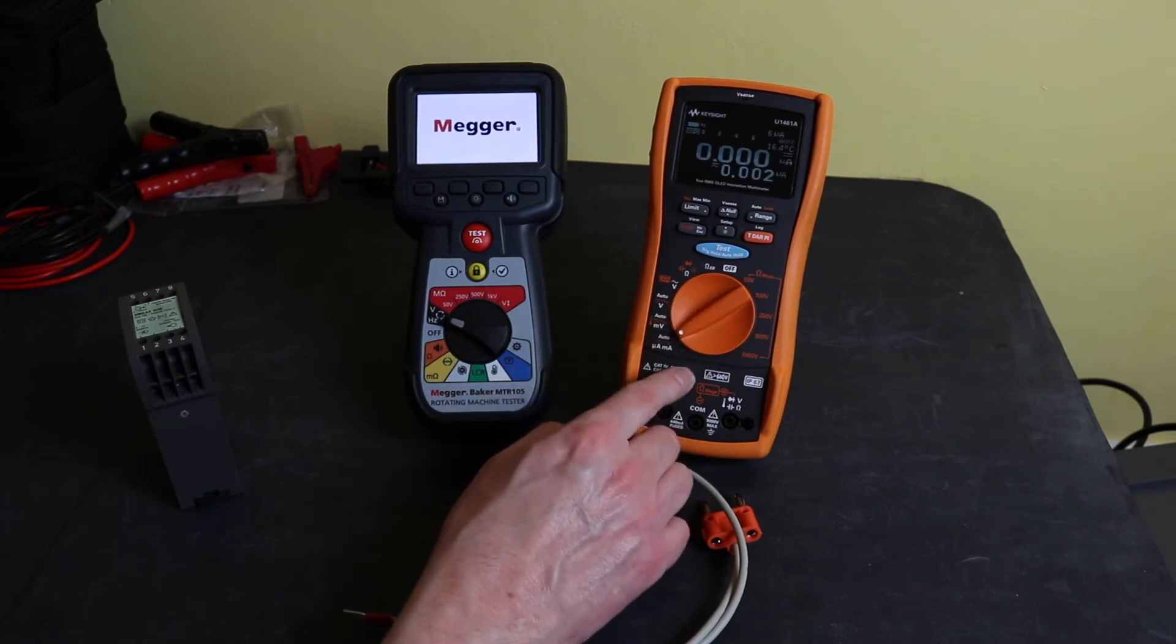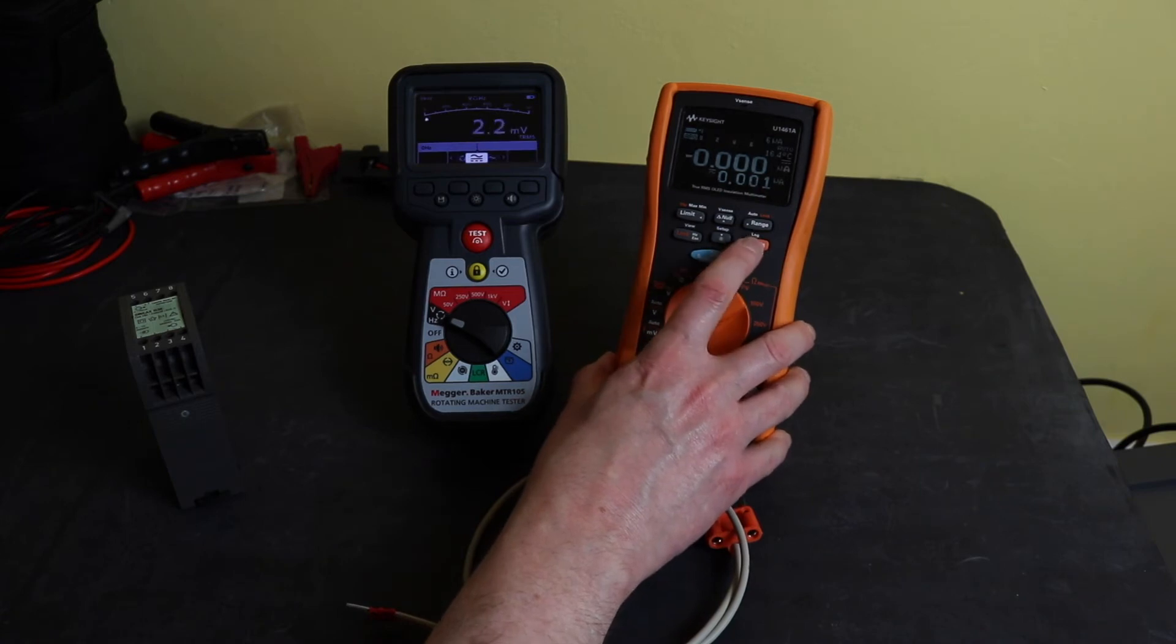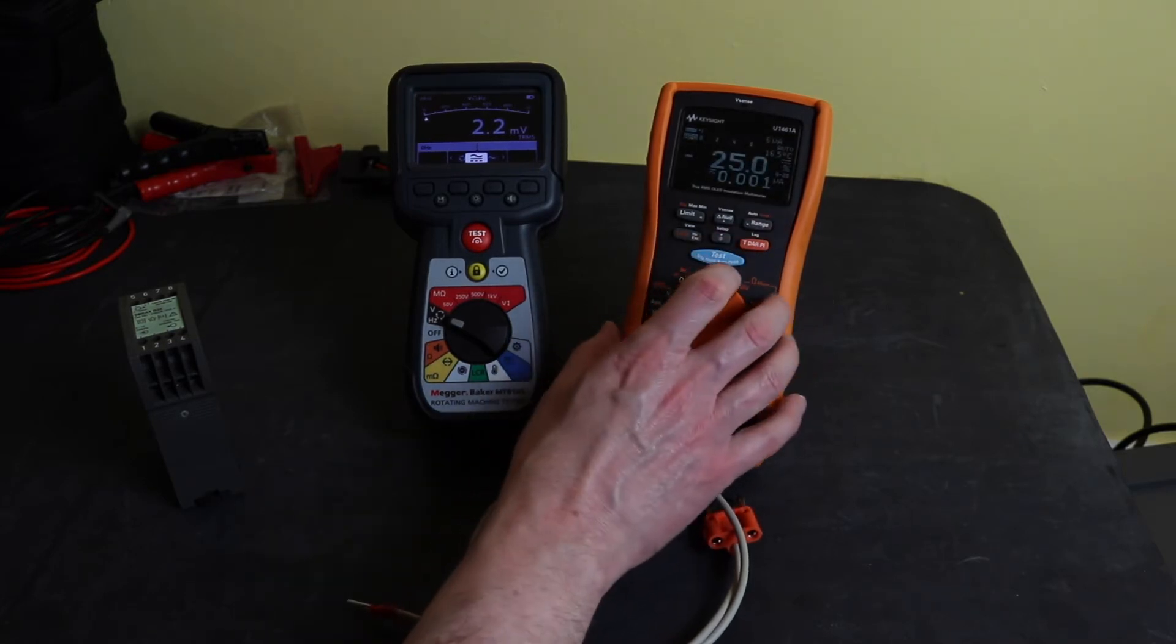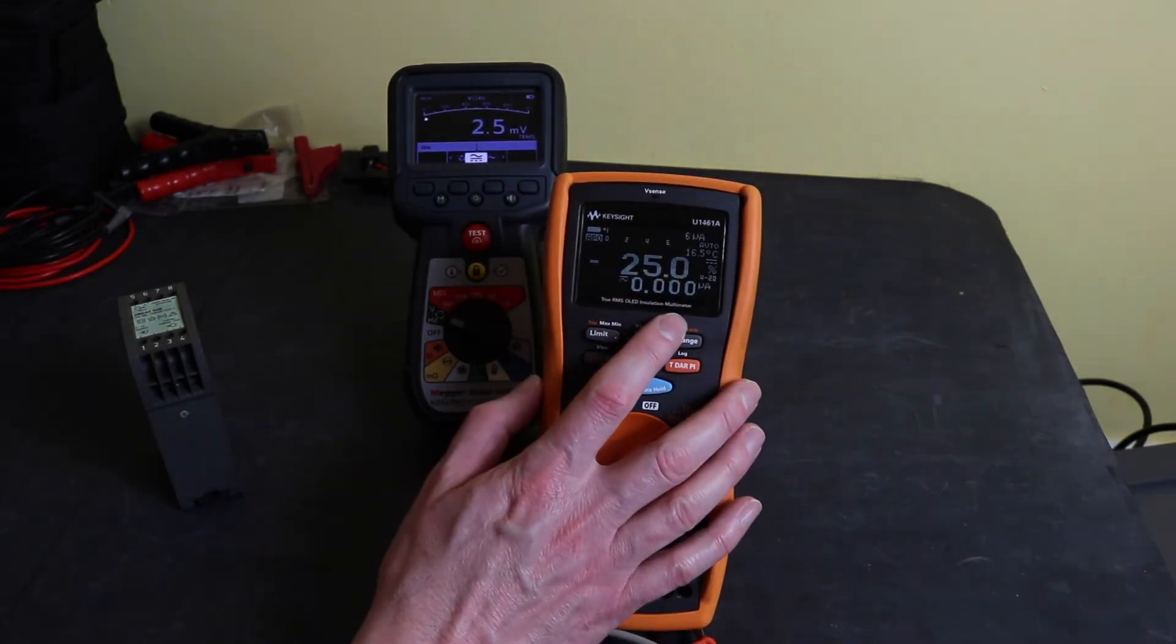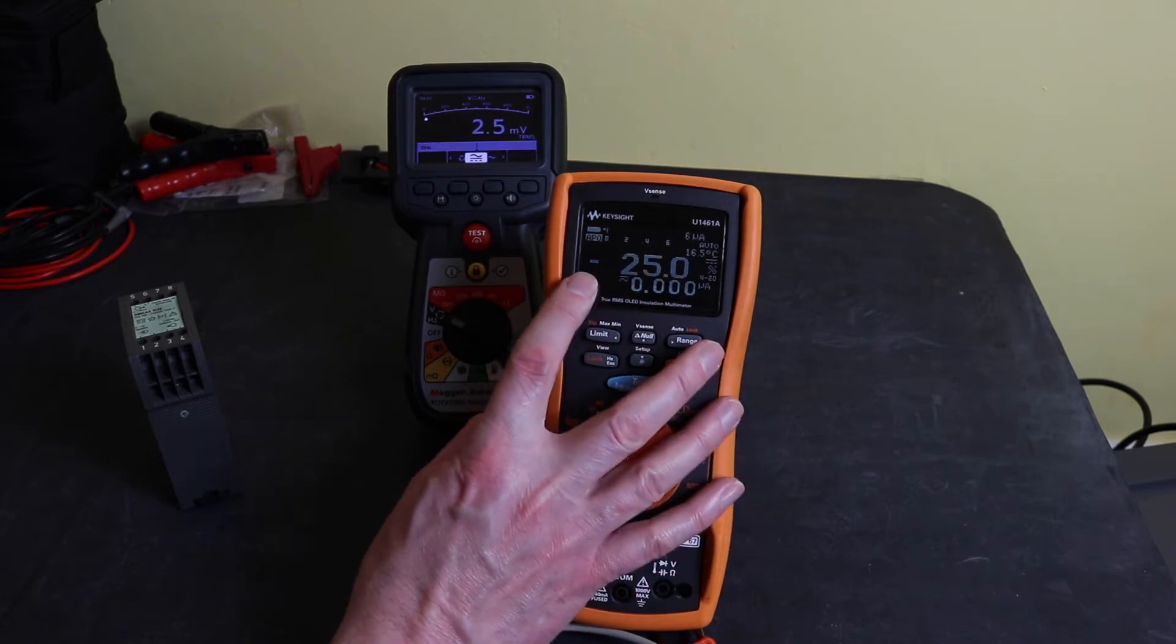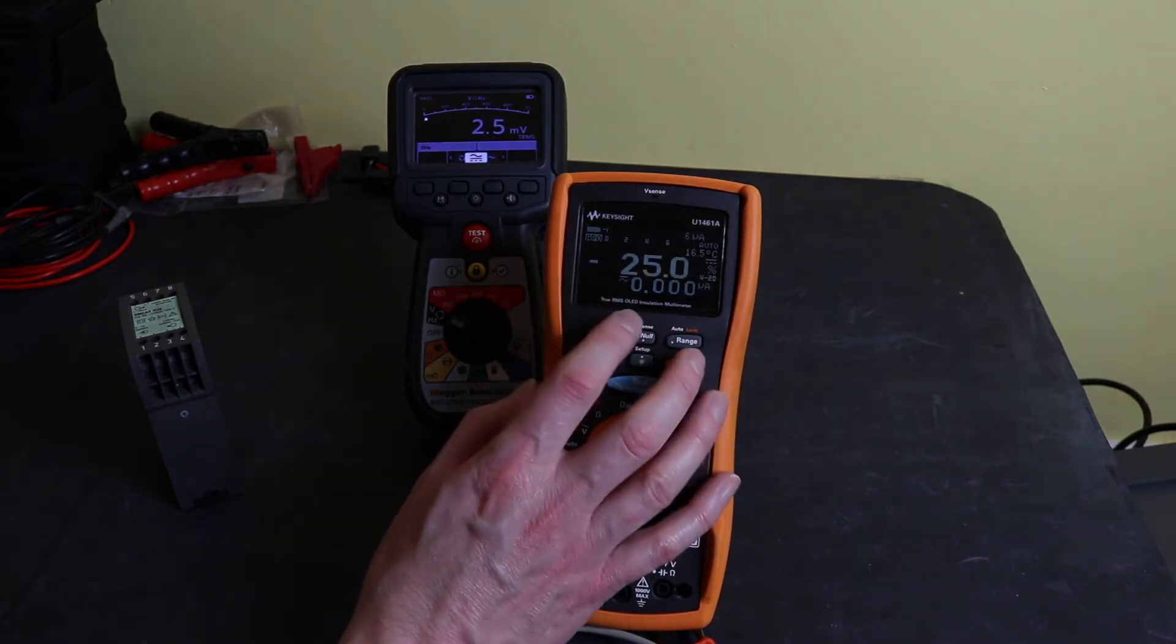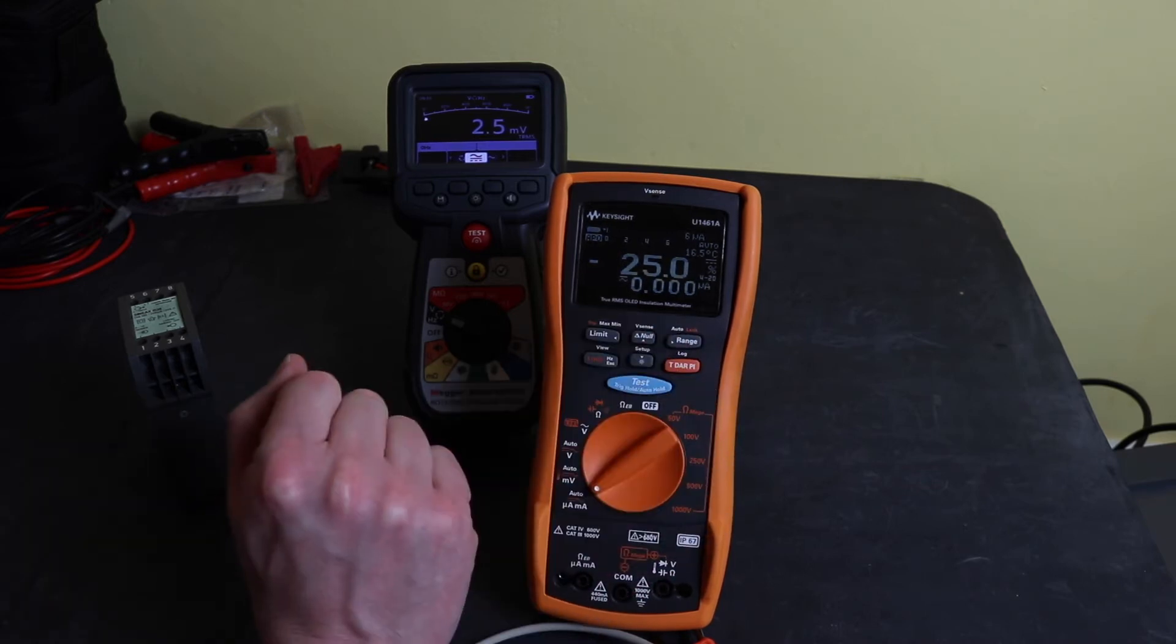But this instrument here also has, you have to set it up in the menus but it has a special 4 to 20 milliamp loop checking function which I've got on here now. If I bring him in a bit closer, you see at this moment time it's displaying 0 milliamps input at the bottom and at the top I've got minus 25 percent. That's because it's looking for the 4 to 20 milliamp and it obviously isn't finding it until I connect it up.